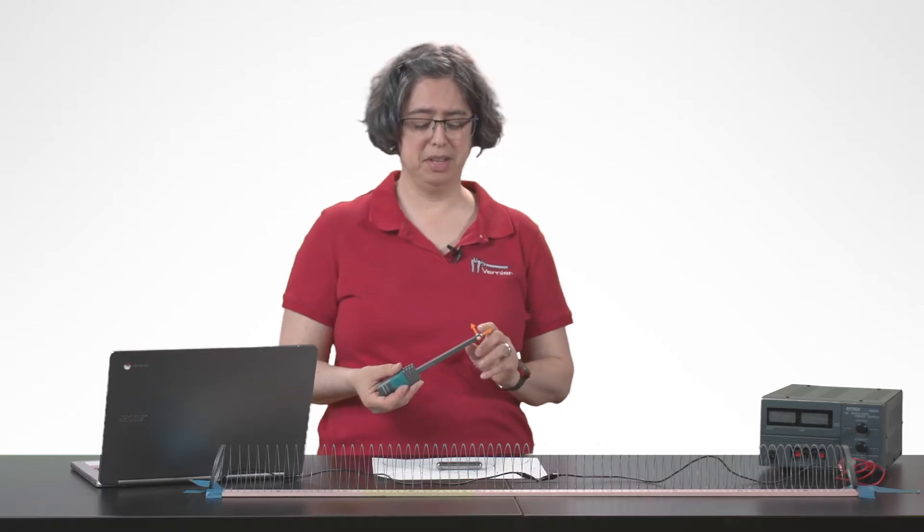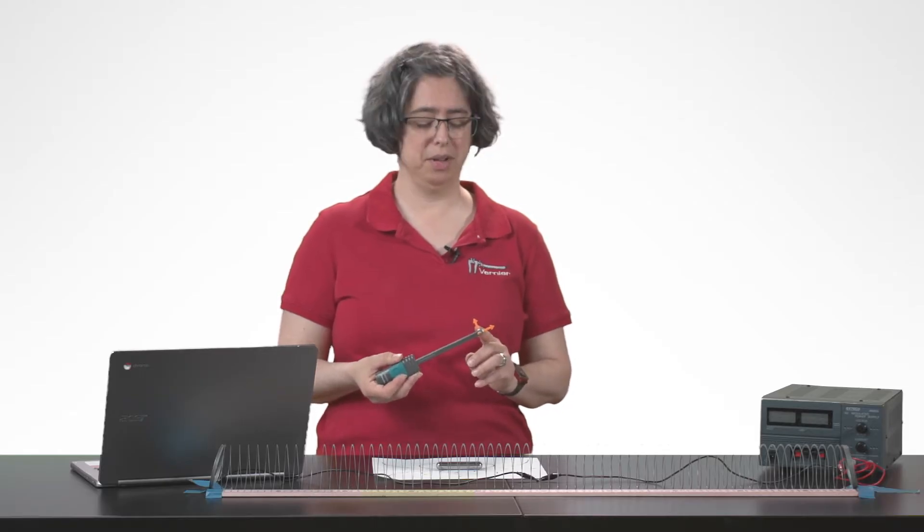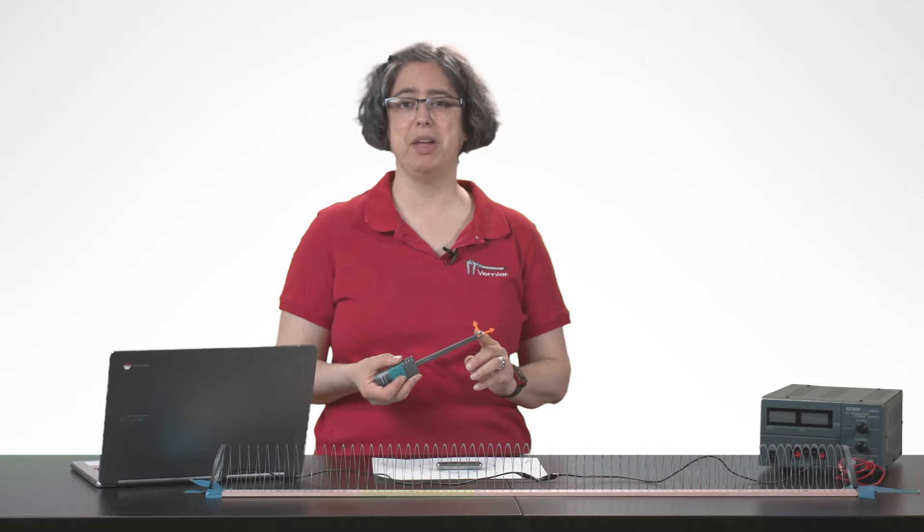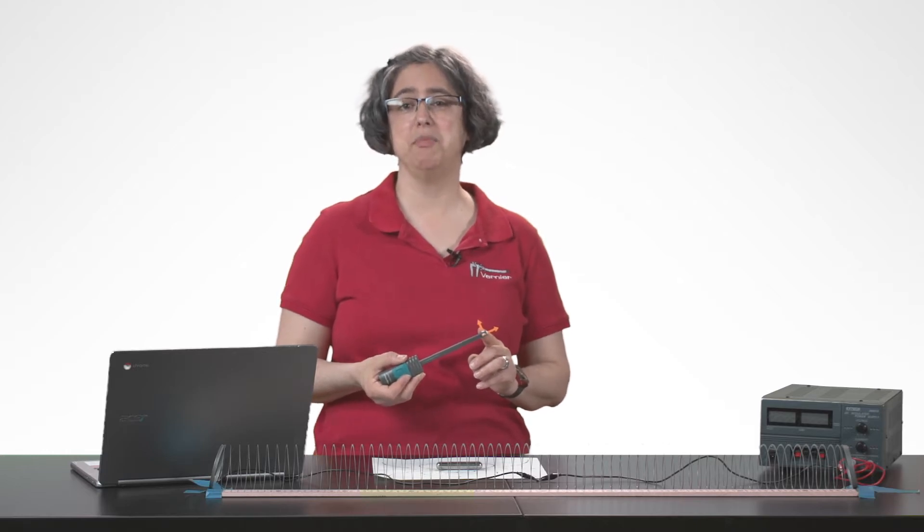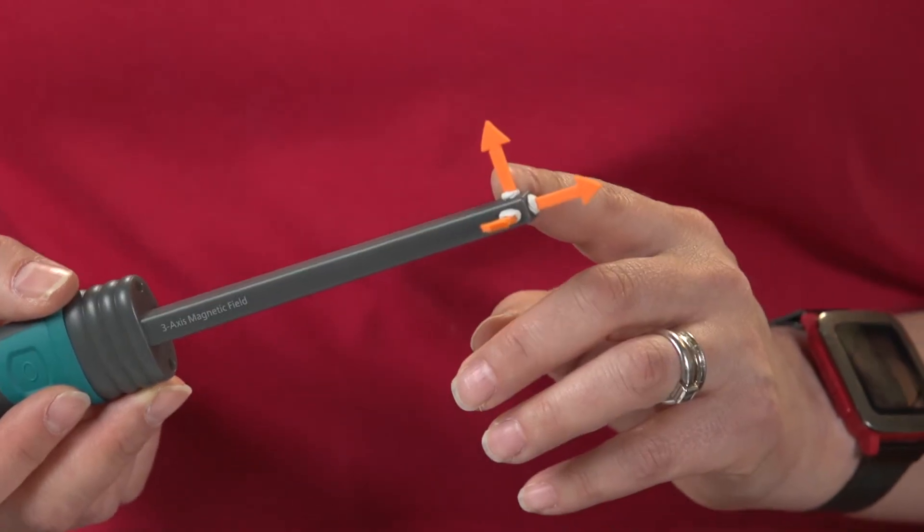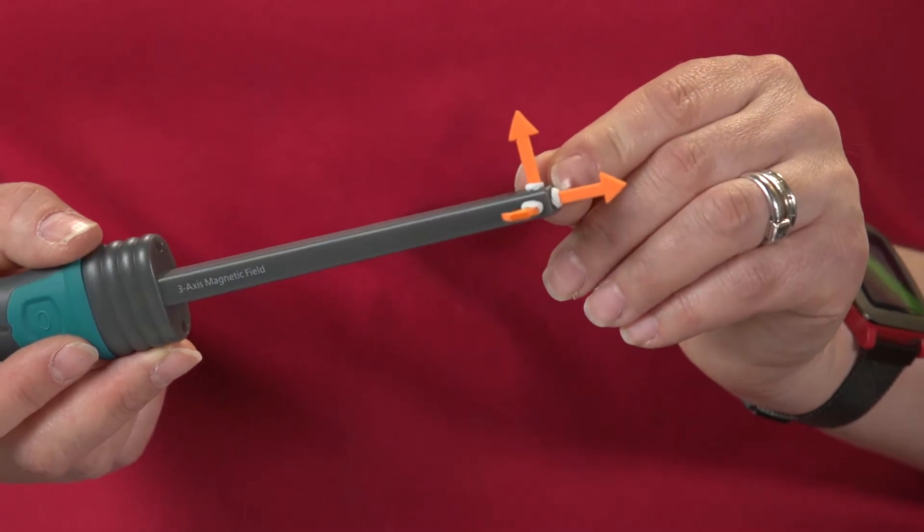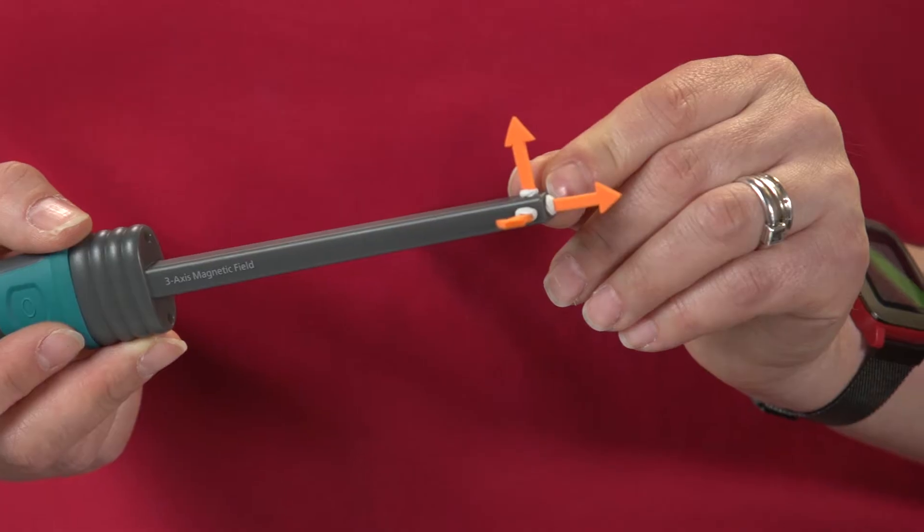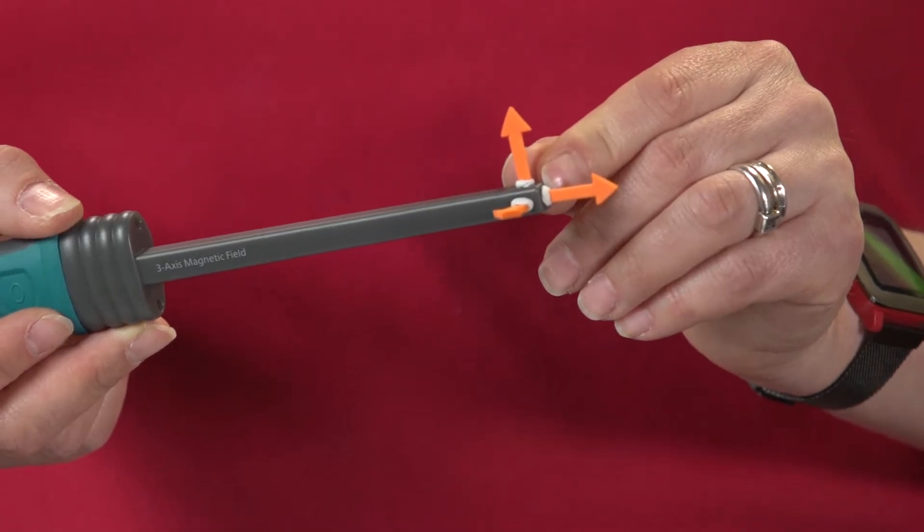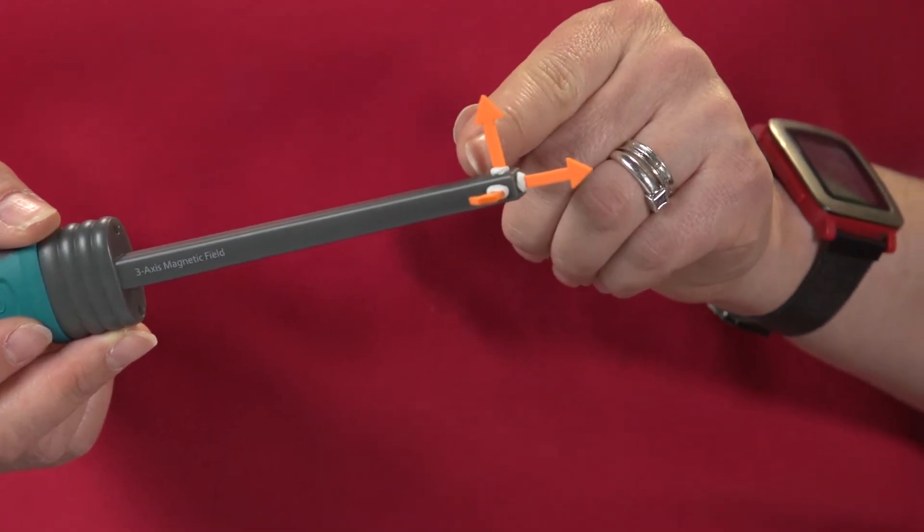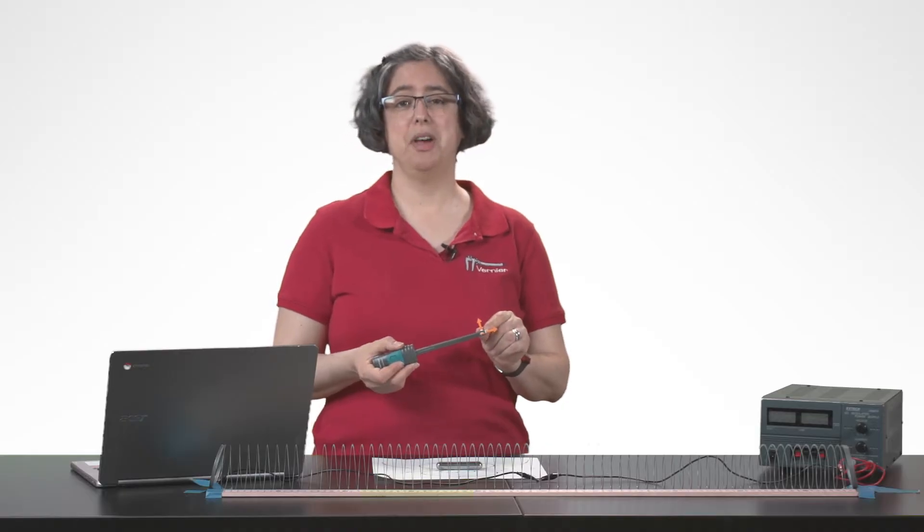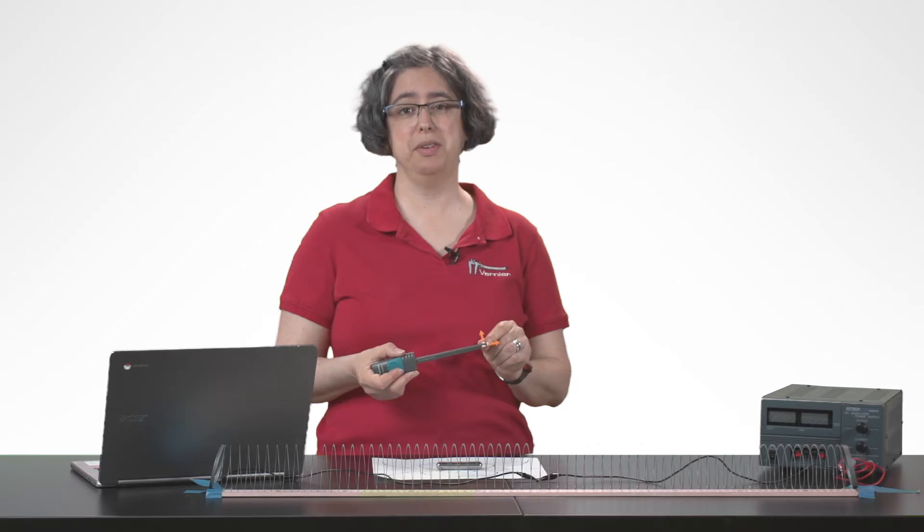It does this at two different magnitudes of magnetic field. I've placed these arrows at the location of the chip that measures at plus or minus 5 millitesla. There's a second chip that's located 10.5 millimeters from the end, so right about there, that measures plus or minus 130 millitesla.